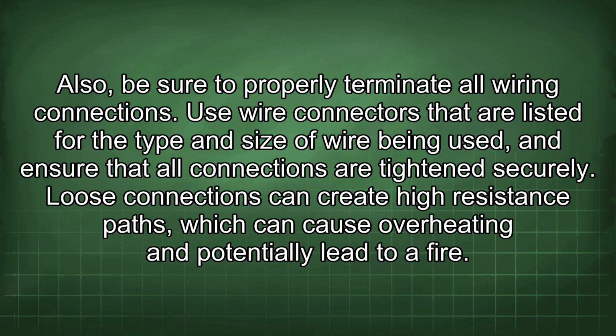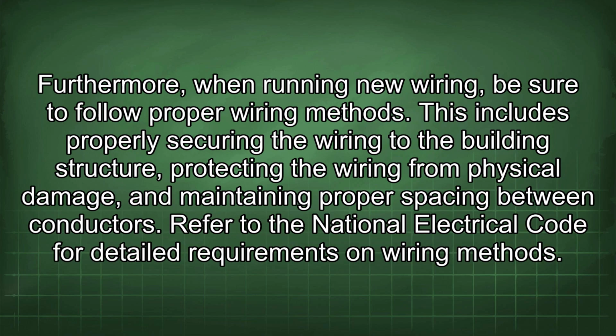Use wire connectors that are listed for the type and size of wire being used, and ensure that all connections are tightened securely. Loose connections can create high-resistance paths which can cause overheating and potentially lead to a fire. Furthermore, when running new wiring, be sure to follow proper wiring methods. This includes properly securing the wiring to the building structure, protecting the wiring from physical damage, and maintaining proper spacing between conductors. Refer to the National Electrical Code for detailed requirements on wiring methods.